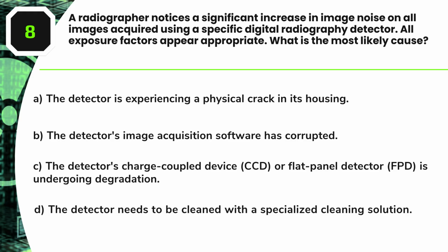Question 8. A radiographer notices a significant increase in image noise on all images acquired using a specific digital radiography detector. All exposure factors appear appropriate. What is the most likely cause? A. The detector is experiencing a physical crack in its housing. B. The detector's image acquisition software has corrupted. C. The detector's charge-coupled device, CCD, or flat panel detector, FPD, is undergoing degradation. D. The detector needs to be cleaned with a specialized cleaning solution.